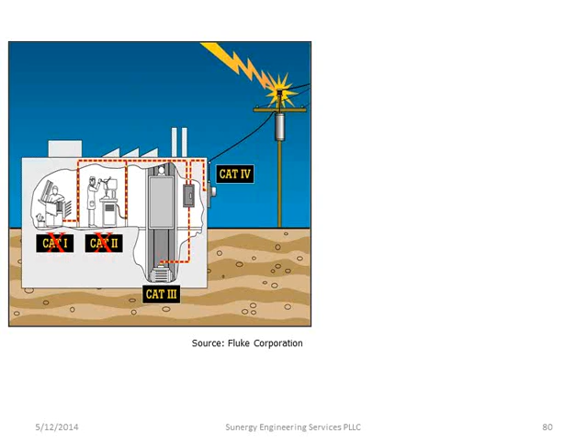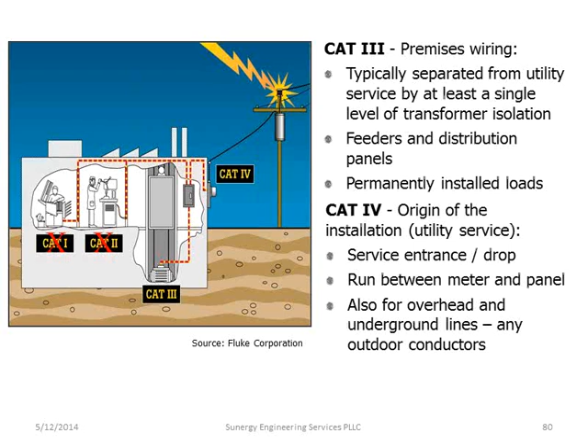One of the big things with all these tools is, especially now that code is allowing 1,000-volt DC systems, we need equipment that's rated appropriately for working around it. For those not familiar with the different ratings: Cat 4 is coming directly from the grid down to the power box, and Cat 3 basically has some isolation somewhere in the system, so it's a lot less arc fault potential.